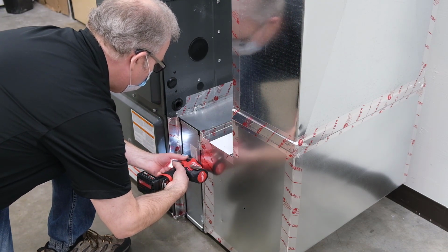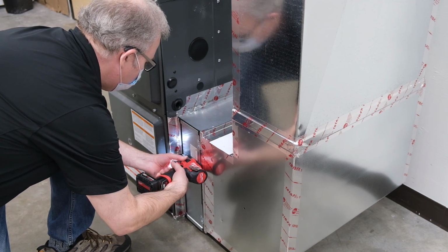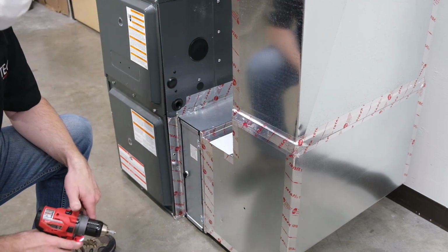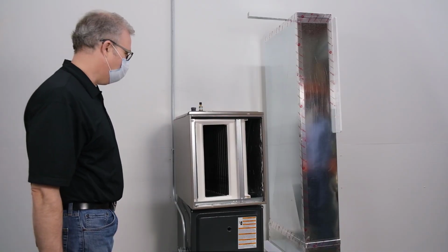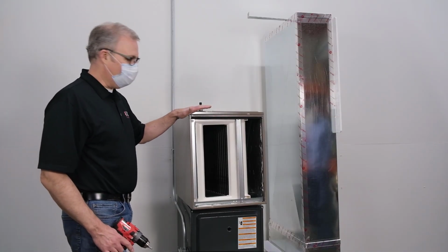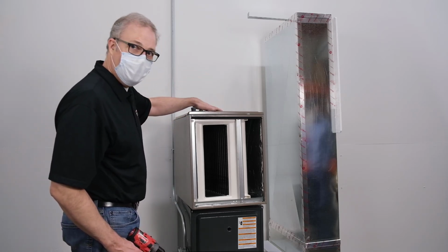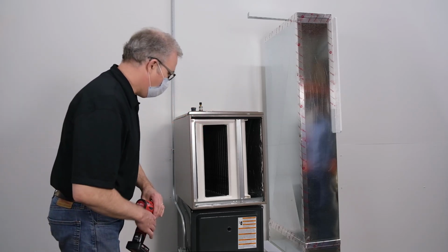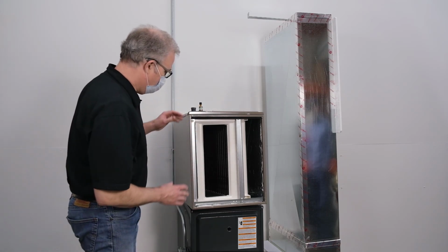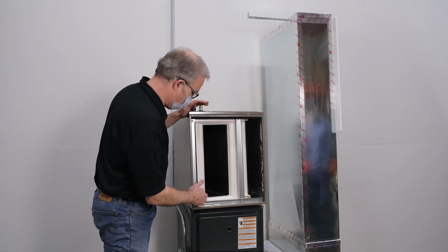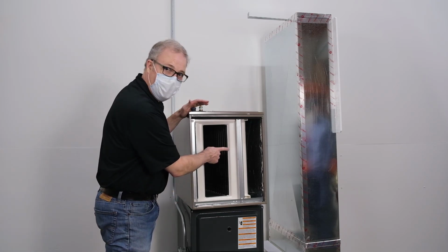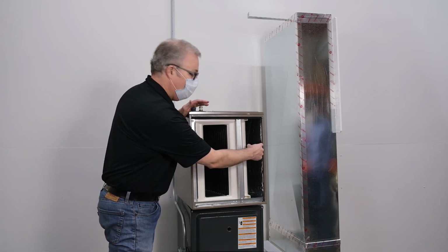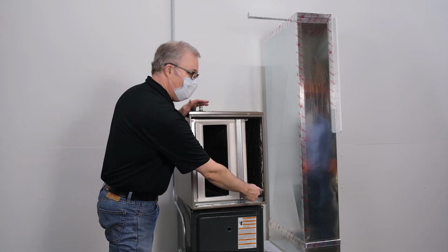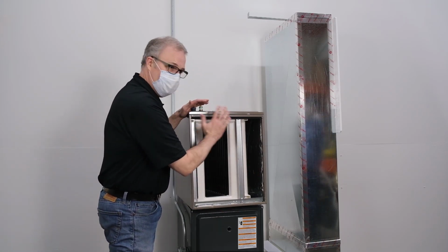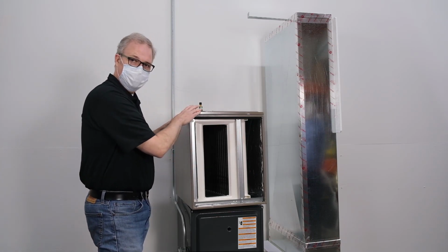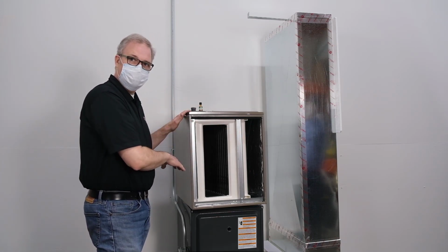We have an indoor coil, and he's going to talk about why to measure into the furnace cabinet and not the coil compartment. This audio is a little rough. Okay, when drilling this, we need to be careful to avoid the refrigerant lines and the drain pan. So I'm going to put down my drill because you can see that the drain pan comes really close to the edges. And if this were an A coil, this drain pan would be up against the side, and all the way around the side would be very near the drain pan. So we don't want to drill into this cabinet if we can drill into the furnace cabinet instead.